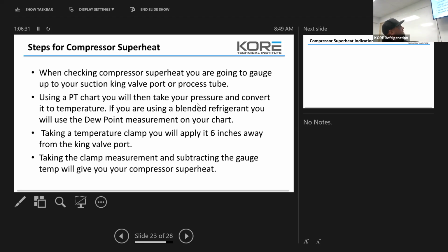Taking the clamp measurement and subtracting the gauge temp will give you your compressor superheat. So how many of you do this when you do startups? How many of you change your contactor, change your filter dryer, check your compression ratios, and check your superheat at your compressor before you walk away? Don't lie to me. You should be doing that on startup. You just replaced anywhere from a $600 to a $10,000 component, depending on the application. Don't you think it's important to the customer that you calibrate that component?